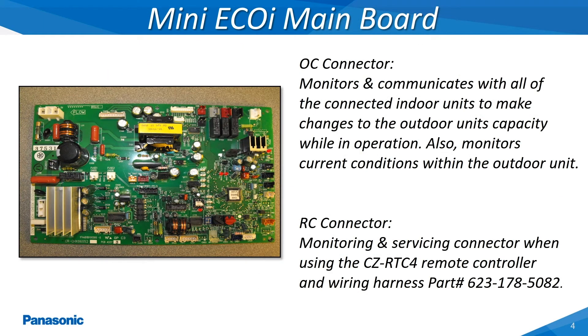The Mini ECOi outdoor unit's main printed circuit board is the primary board which receives continual packets of information back from all of the connected indoor units. This board also monitors the current operation within the outdoor unit to make any necessary changes for optimal performance. Many of these details being reported to the outdoor board can be seen by plugging the servicing remote controller with wiring harness into the RC connector located on this board.